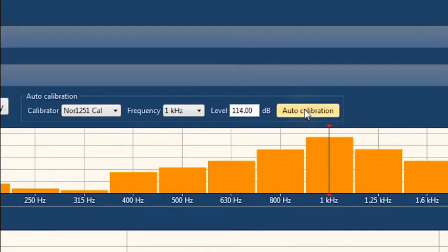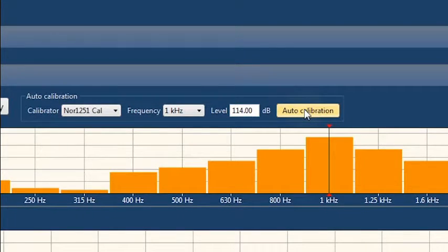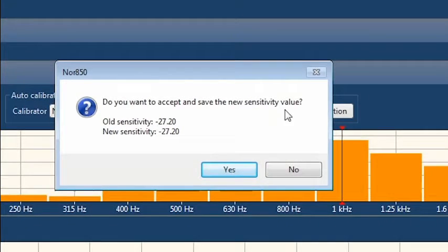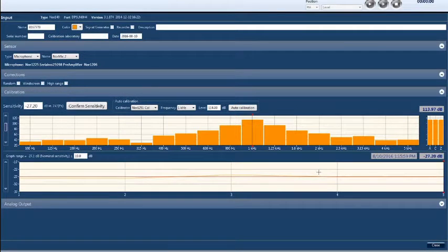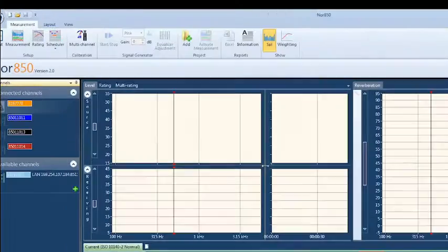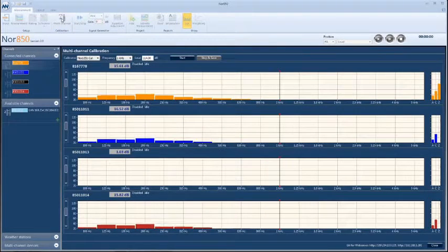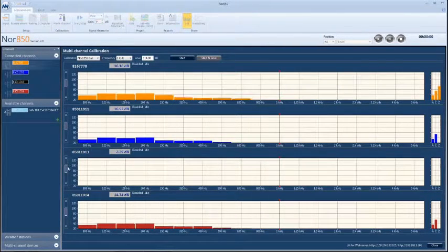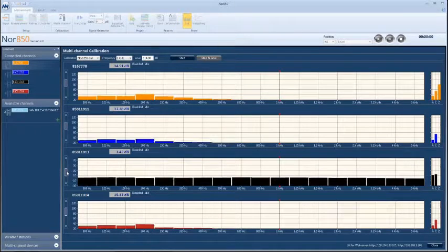The auto calibration feature automatically detects the reference tone and adjusts the sensitivity accordingly. The multi-channel calibration feature is useful for automatic calibration of several channels, one after the other, as the calibrator is attached to each sensor.